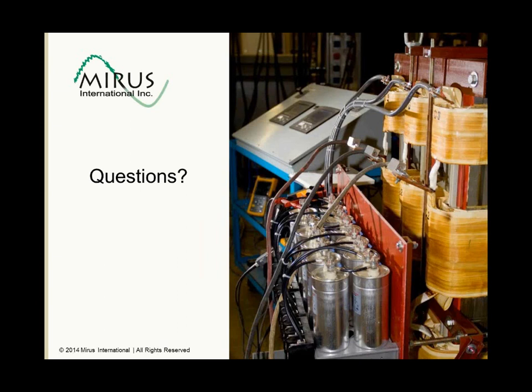And there's a question here: under what conditions are capacitor bank switching contactors necessary in passive harmonic filters? Very good question. Many of the passive filters that are available on the market today have quite high levels of capacitive reactance, especially when they're sitting idle or at light loads. Generator systems typically can handle capacitive reactance that's 20% or less, but often these filters have 30-40% capacitive reactance.